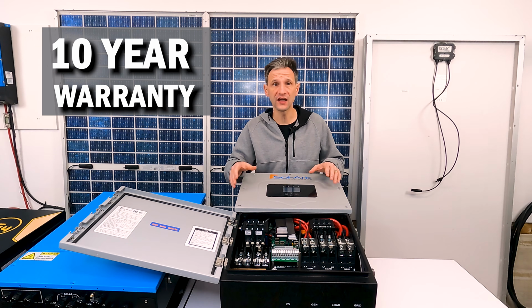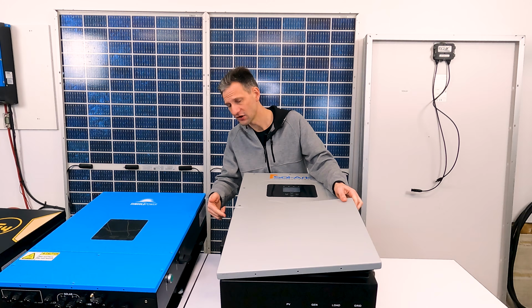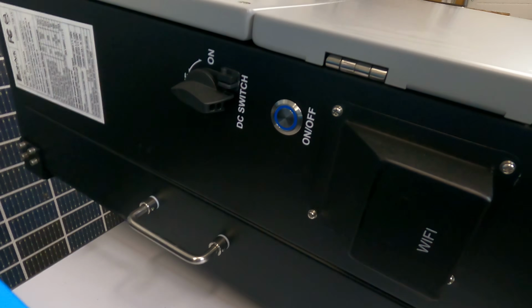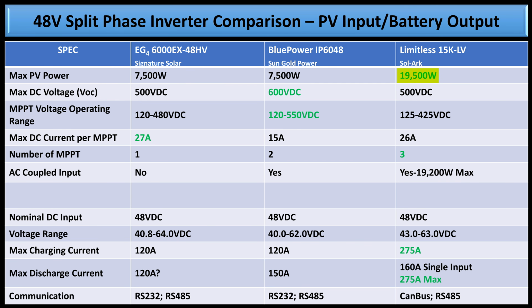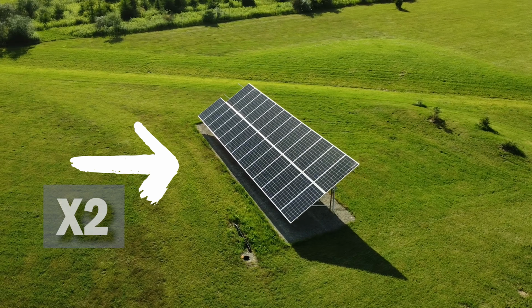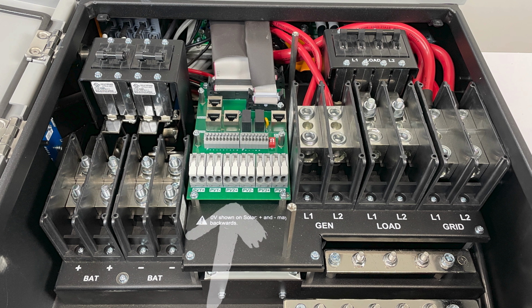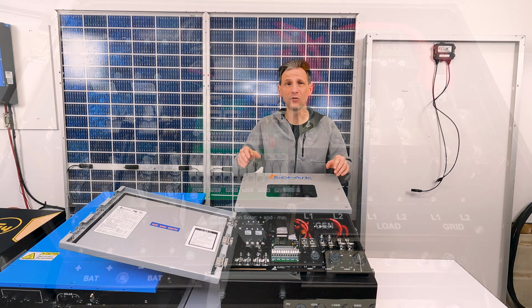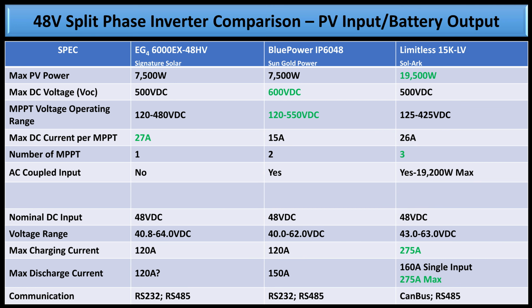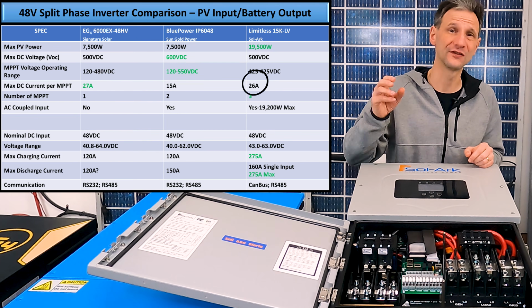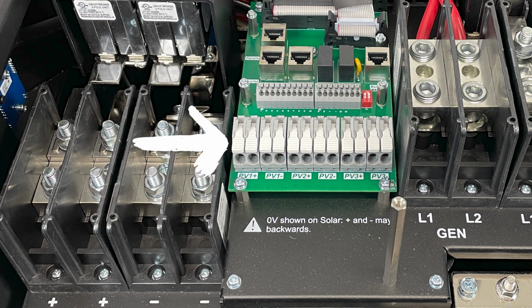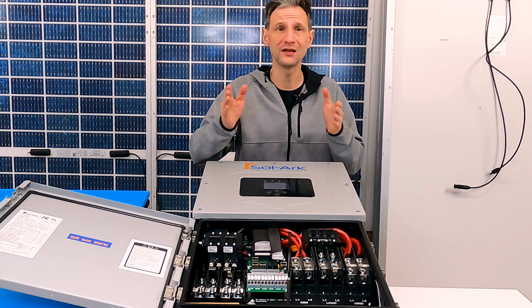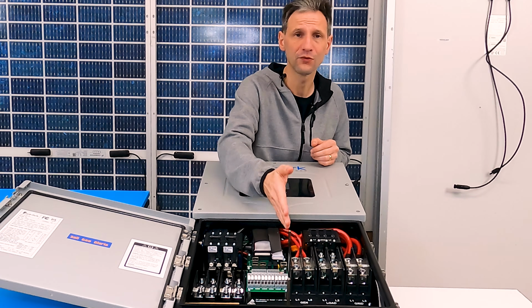The SolArk 15K has a built-in DC switch for the PV input and a max PV input of 19,500 watts, managed through 3 dual-input MPPT controllers. It has a respectable max voltage input of 500 volts and a reasonable operating range from 125 to 425 volts, with a peak input current of 26 amps. And dual connections for each input. You can easily put 2 pairs of strings in parallel on each of the 3 MPPTs.